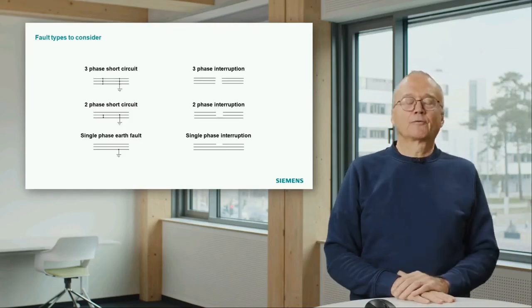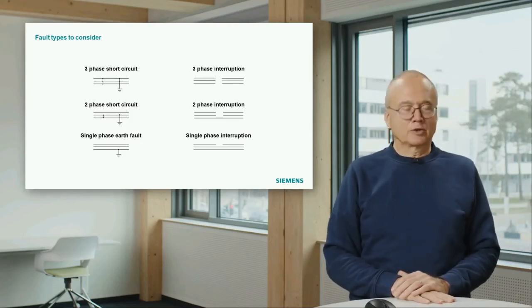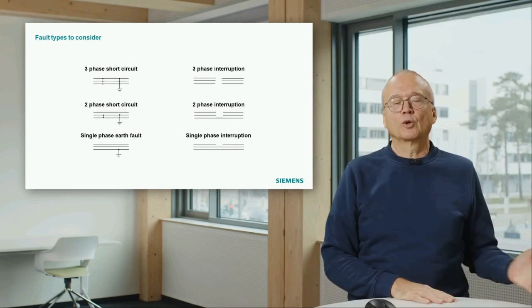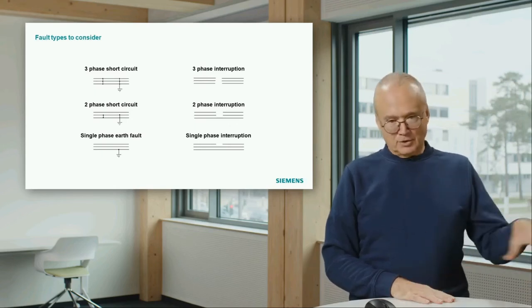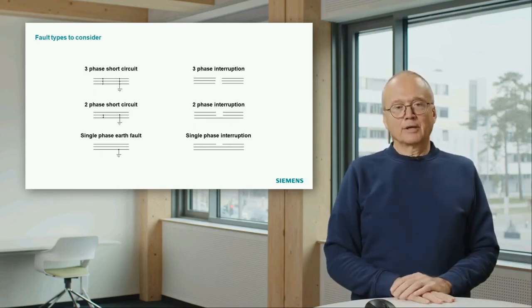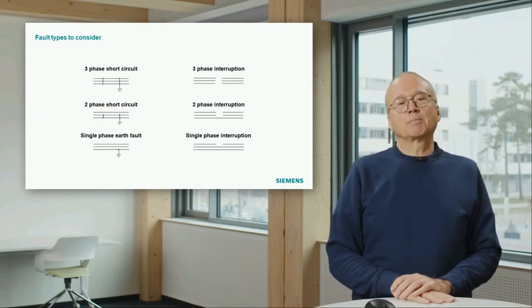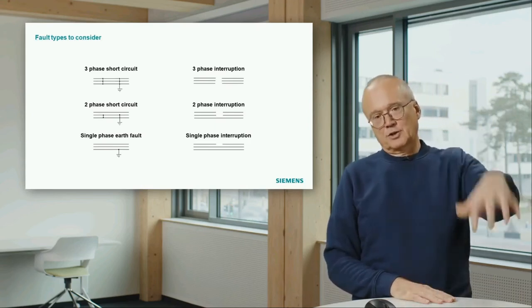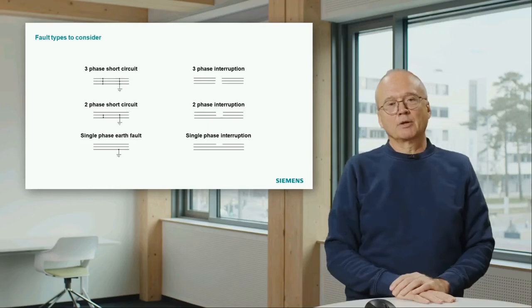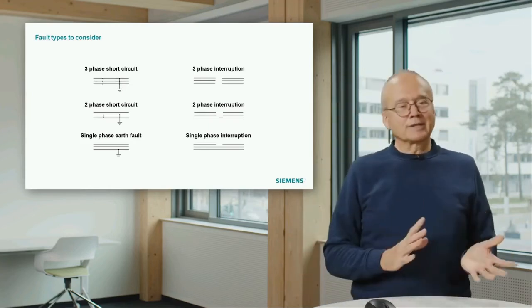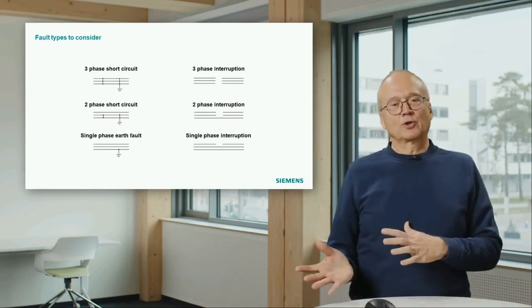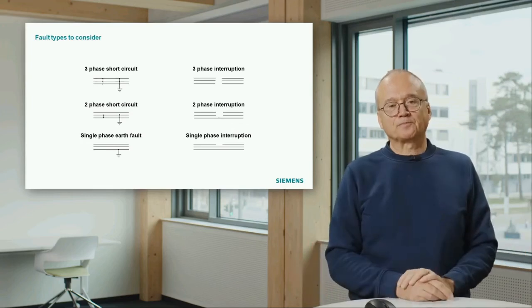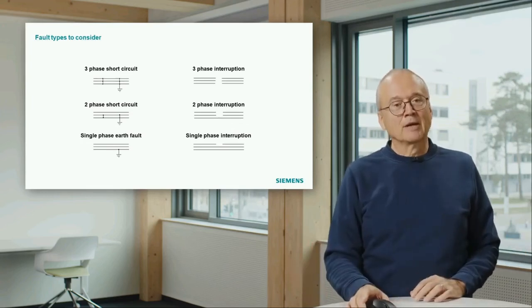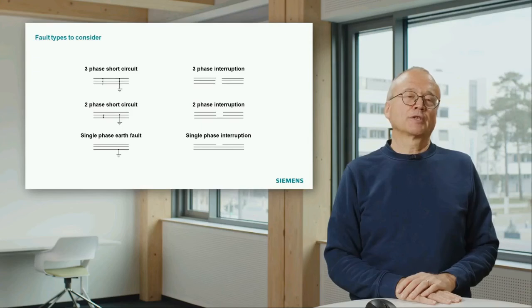The typical thing, for instance, would be in a distribution system. You have roadworks there, people opening the street, didn't look at the cable plans before, the excavator hits the cable, and either you get an interruption or you get a short circuit, or both. That's one reason why you have three-phase short circuits.